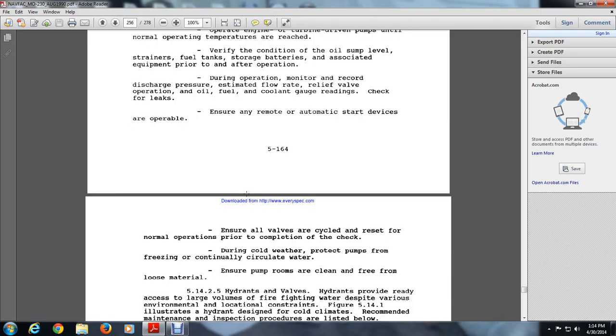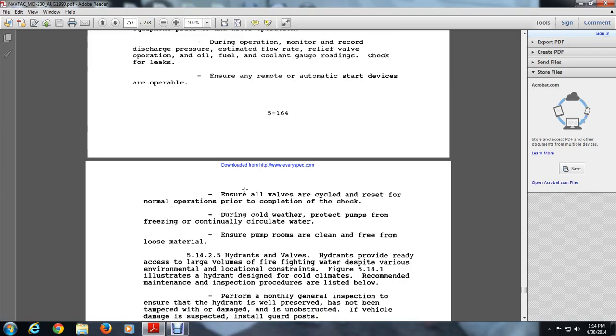During cold weather, protect the pumps from freezing by continual circulation of water, ensuring the pump rooms are clean and free of loose material. 5.14.2.5 Hydrants and valves. Hydrants provide ready access to large volumes of firefighting water despite various environmental and location constraints of fire. Figure 5.14.1 illustrates the hydrant design in cold climates.